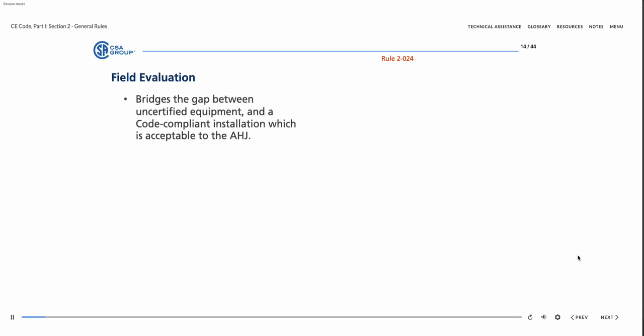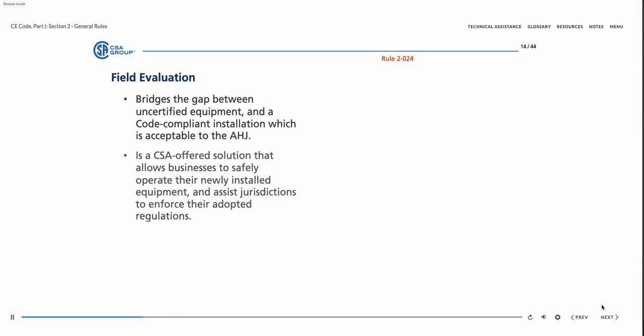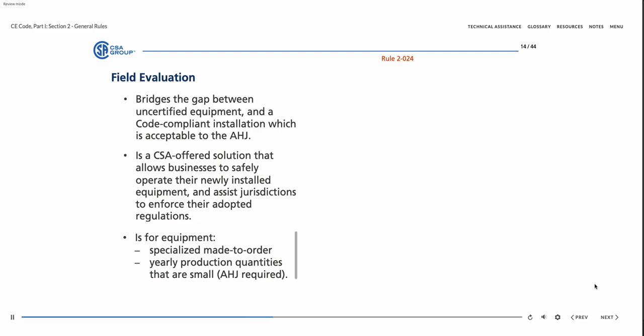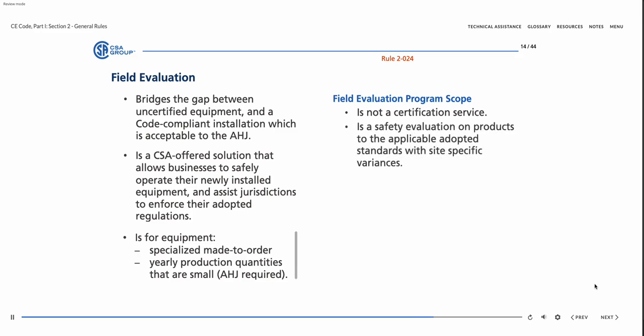Field evaluations bridge the gap between uncertified equipment and a code-compliant installation acceptable to the authority having jurisdiction, AHJ. CSA offers a solution that allows businesses to safely operate their newly installed equipment and assist jurisdictions to enforce their adopted regulations. A typical situation is equipment that is a specialized made-to-order product, with small yearly production quantities, which is a requirement by the authority having jurisdiction, AHJ. The scope of the field evaluation program is not a certification service. It is a safety evaluation on products to the applicable adopted standards with site-specific variances, offered in support of approved products.